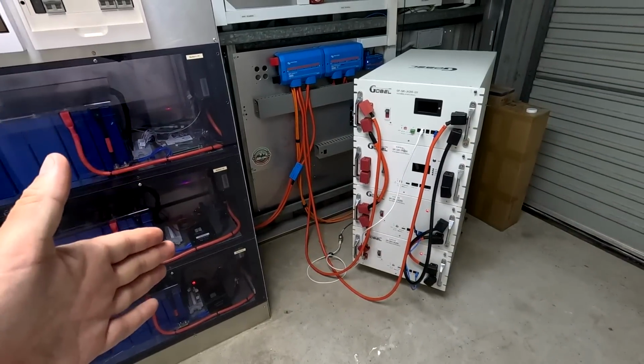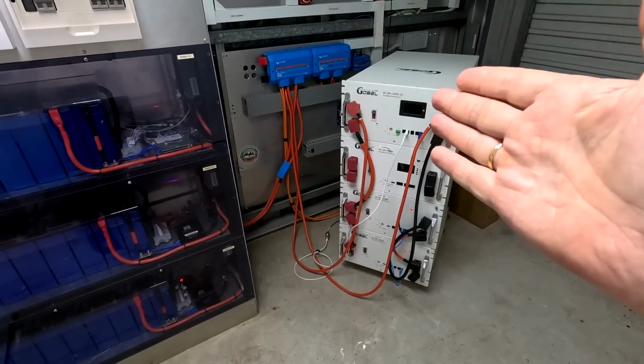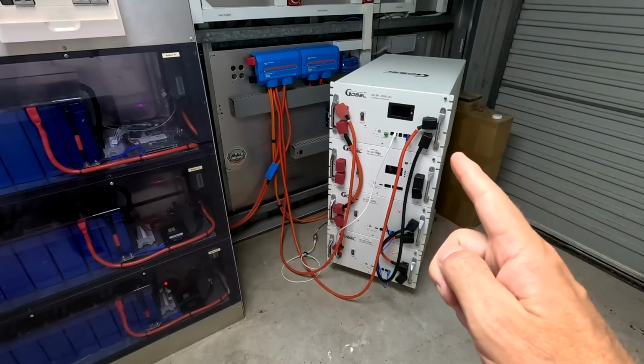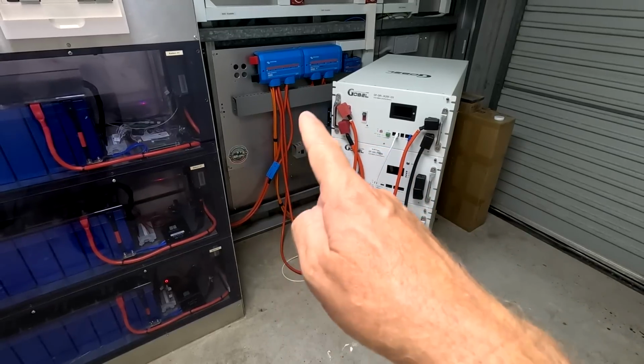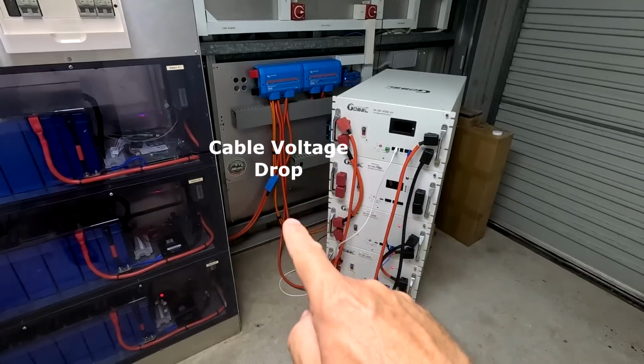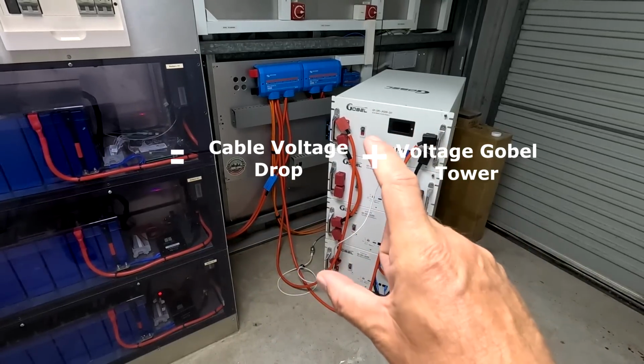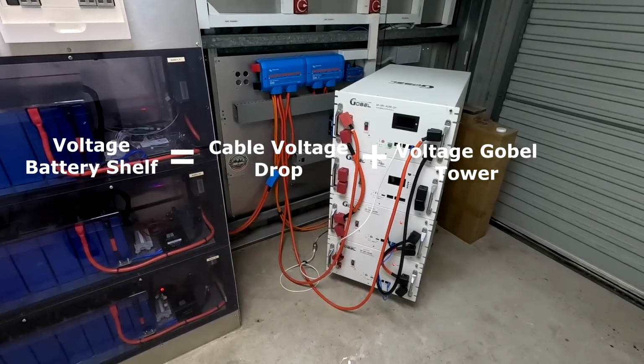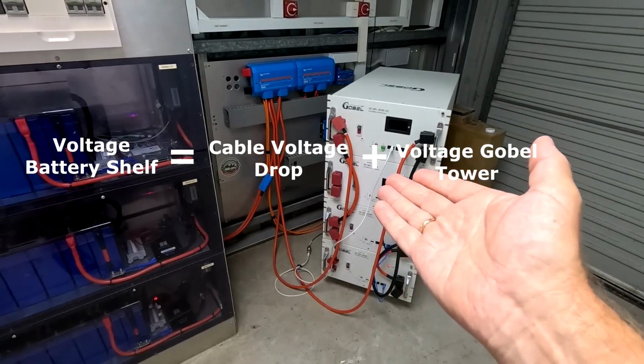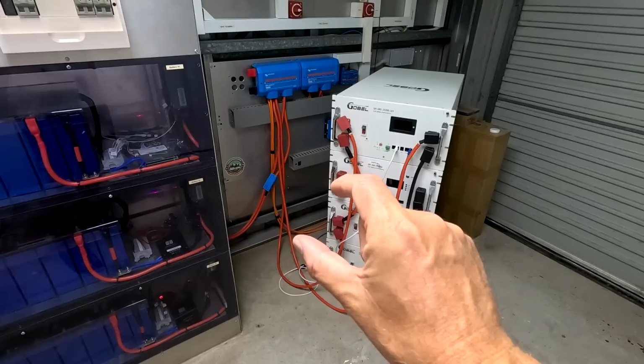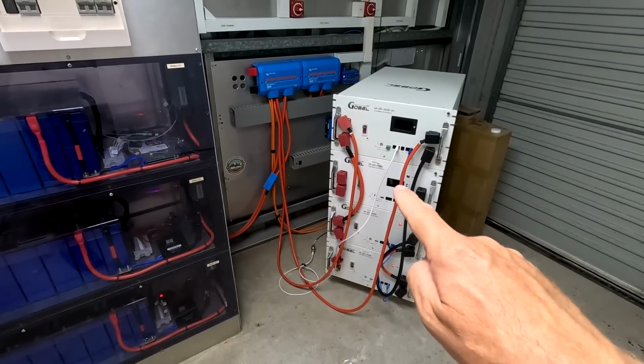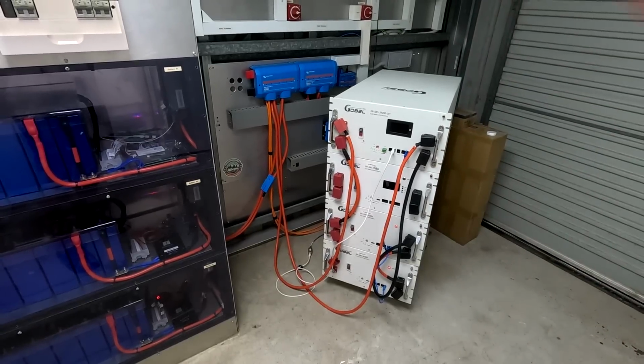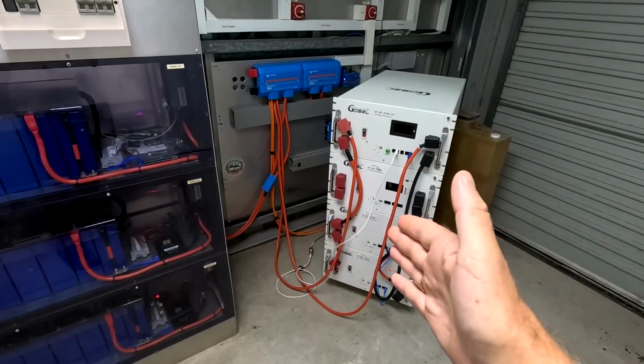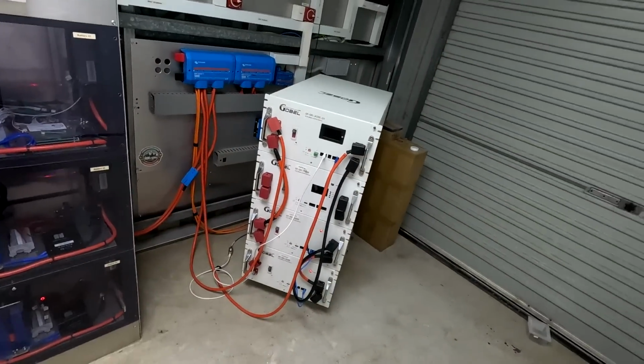So now we've got this effect that the battery shelf has a certain voltage. And this exact voltage is applied to the Gobel tower as well, but not completely, because we have some voltage drop on the cabling and connection and all this other stuff in between. So the voltage drop plus the battery voltage of the Gobel tower is exactly the same as the one from the battery shelf. And now as we see that the Gobel tower is catching up, the voltage is slowly rising, the amps are going down, the voltage drop on these cables is going down, and the voltage can actually rise even further. And eventually the current will be zero and the batteries will have the exact same voltage as in the battery shelf, which is 55.2 volts.